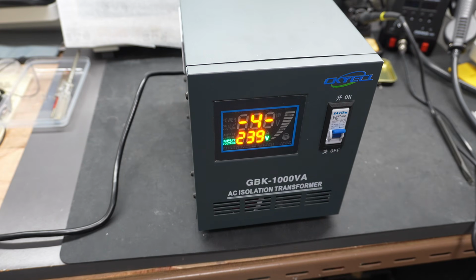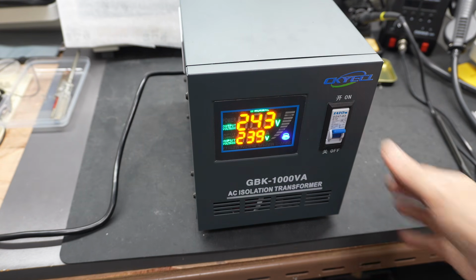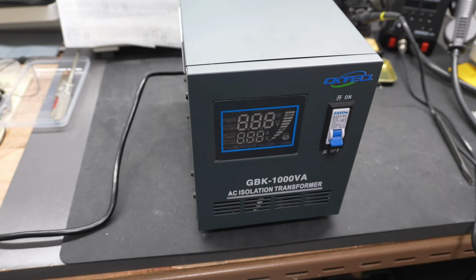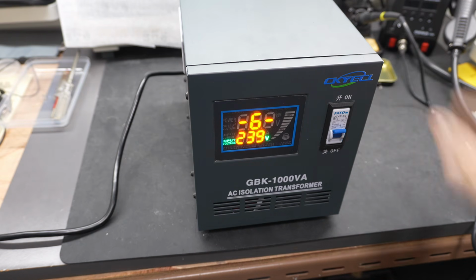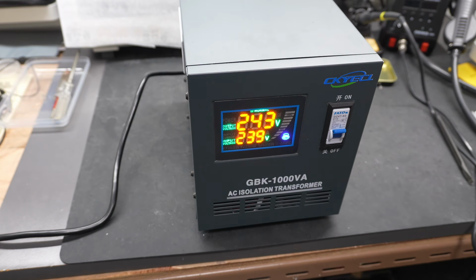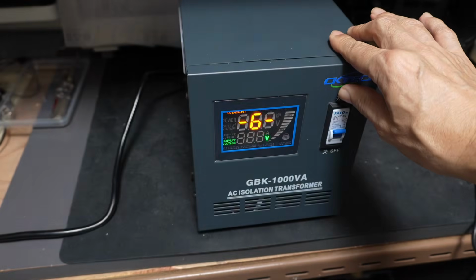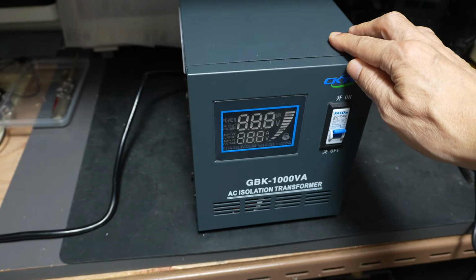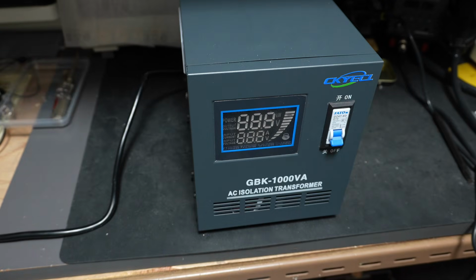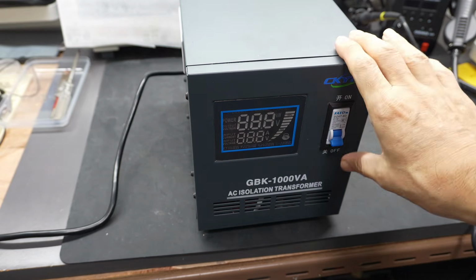Okay, this one worked. Nothing has to be connected, it's just a matter of when you switch it on - I believe it depends on when in the cycle of the power, in terms of the sinusoid, 50 Hertz. If this happens to switch on at the wrong time in the cycle, it has maximum surge current and trips the breaker within the room. There you go, see the power's being tripped? I'll switch it off, switch on the power again, reset the switch, try again - it's okay this time.